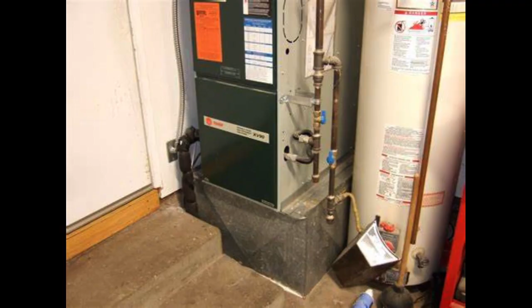3. Requirements for gas units. The inspector shall report as deficient A. Gas leaks in the heating equipment not associated with the gas distribution system, B. Flame impingement, uplifting flame, improper flame color, or excessive scale buildup, and C. Deficiencies in (i) combustion and dilution air, and (ii) the vent pipe, draft hood, draft, proximity to combustibles, and vent termination point and clearances.